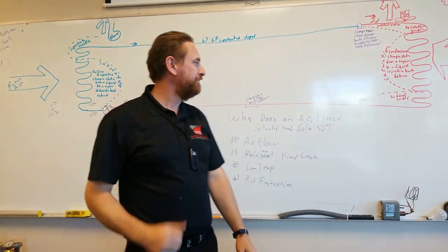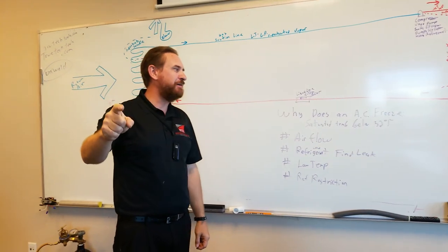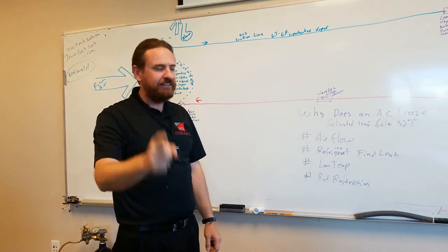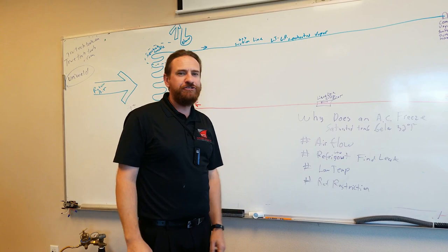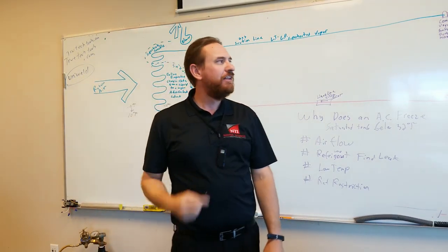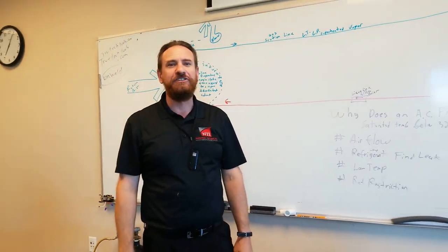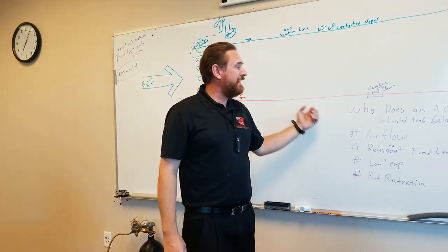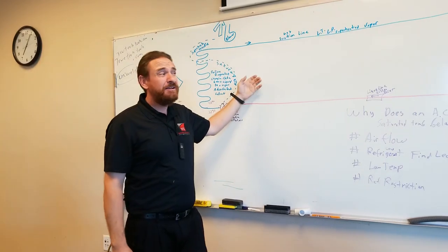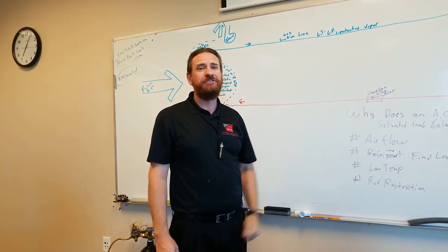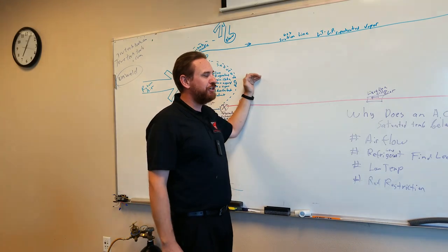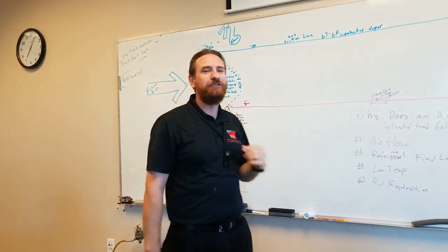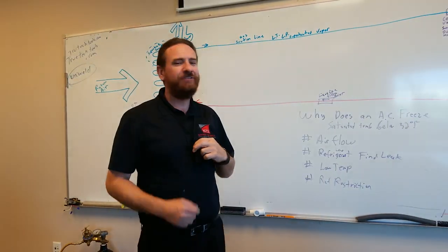Why does an AC freeze? Saturated temperature below 32°F. Number one cause: airflow. Number two: low refrigerant — find the leak. Three: inside or outside temperature too low. Four: refrigerant cycle restriction. Keep those in mind and you'll solve any of these issues. It can also be a combination — a mild airflow restriction plus a slight outdoor temperature drop can trigger freezing, or an airflow restriction plus a slightly dirty filter together push it over the edge. Hope that helps. Have a great day.